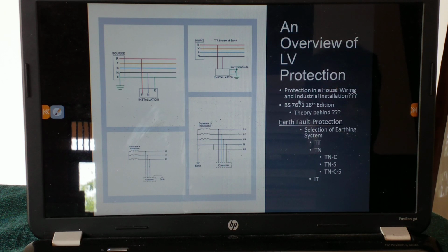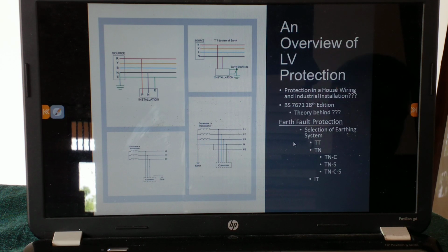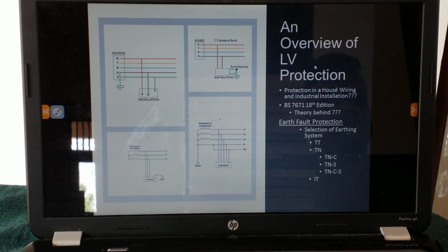Low voltage protection we do based on BS 7671 18th edition. BS 7671 is the British standard which covers all the low voltage protections. And in the low voltage sections we have two main faults, earth fault and overcurrent fault. First we discuss earth fault protection, then overcurrent protection. Earth fault is: if our phase conductor gets earthed, what will happen, and what are we going to do against that fault? And overcurrent protection is: if our conductor is delivering more current than it can bear, what are we going to do? Those protections are overcurrent protection.